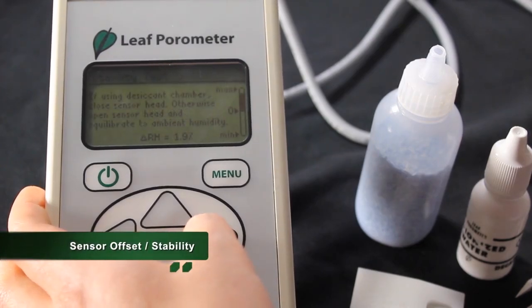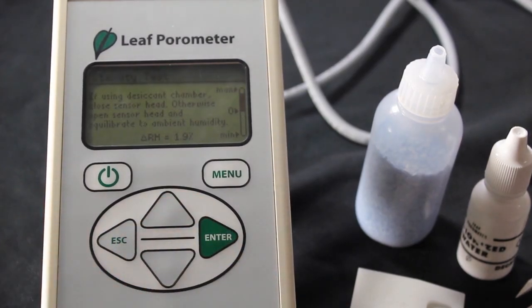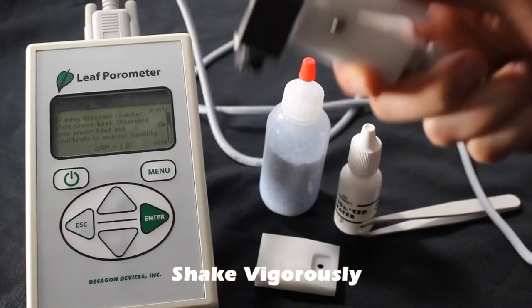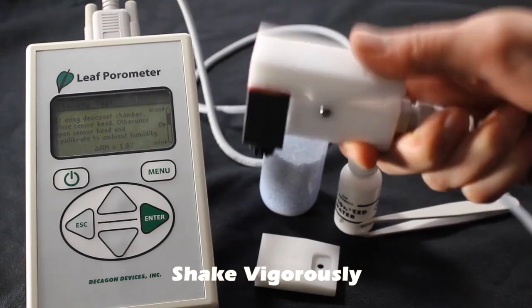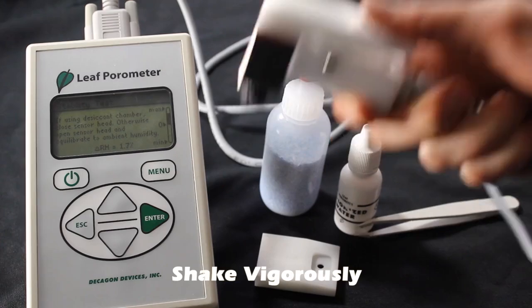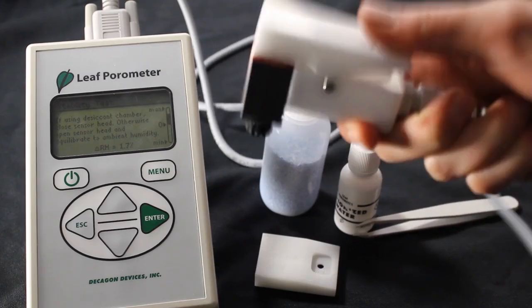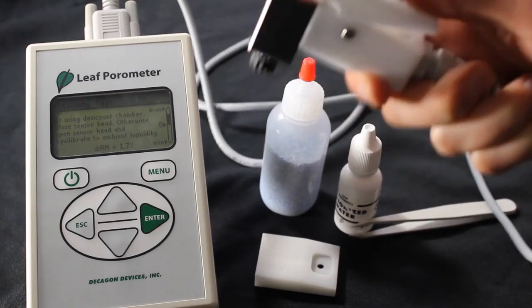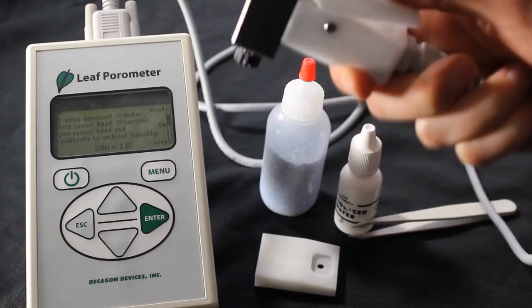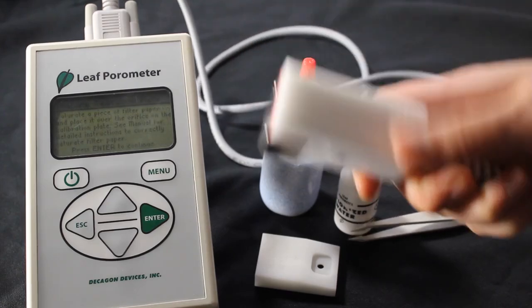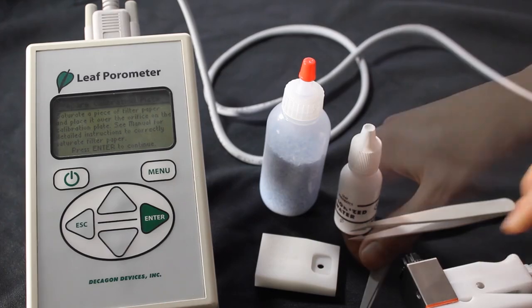Before beginning a calibration, the leaf porometer checks to make sure that the two sensors in the sensor head agree well with each other. For the sensors to agree, the air in the diffusion path should be well mixed. To do this, you will need to wave the sensor head up and down, enabling the bead inside to mix the air. Remember to keep the sensor head closed while waving it in the air to ensure equilibration and prevent loss of the bead. As the sensors come to equilibrium, you should see the indicator bar move closer to the 0% offset line. Once the sensor readings stabilize and are confirmed to be within 2% relative humidity of each other, the calibration routine automatically advances to the next screen.